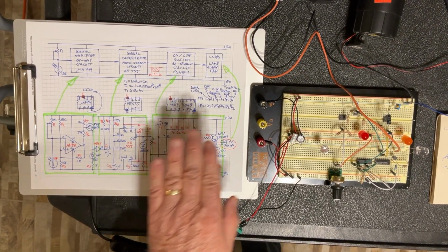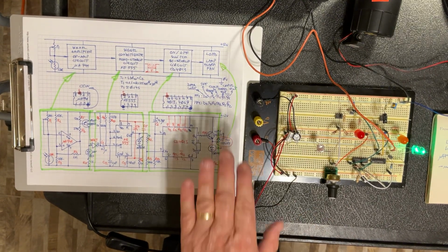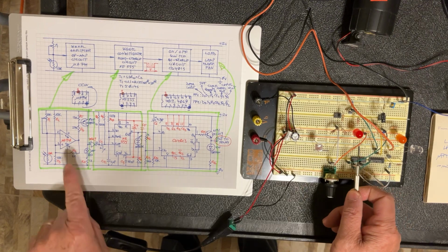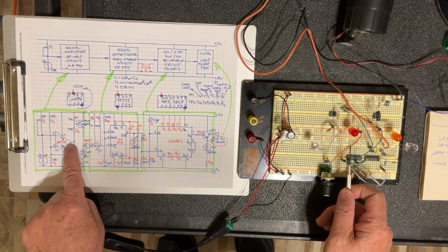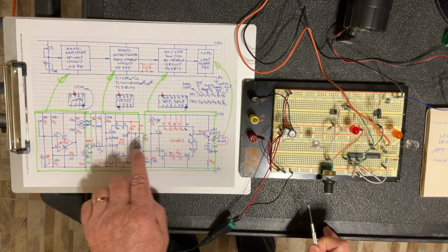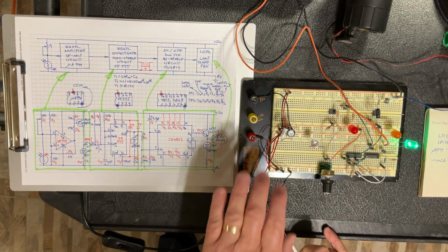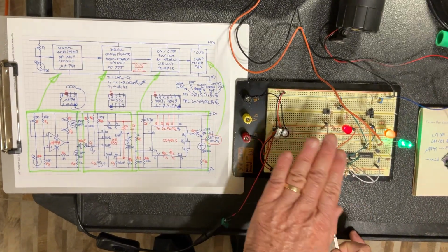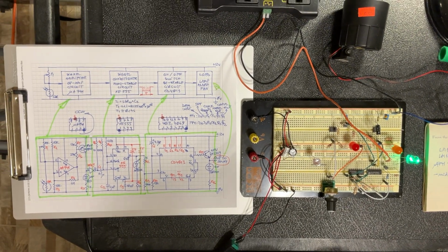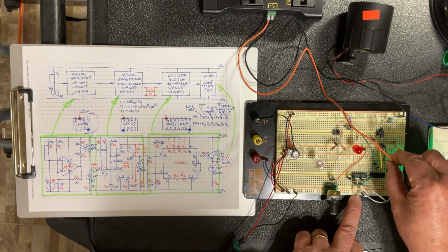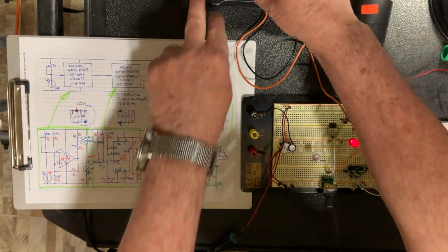Just because we want them to be triggered at the same time, and if you take a look here at this red LED, which is the output of the signal amplifier, and the amber LED, which is at the output of the signal conditioner, they both go on at the same time. But they don't behave the same way. So to make sure we get it, I'm going to quickly disconnect the load. Let me just do it from here, from the relay.